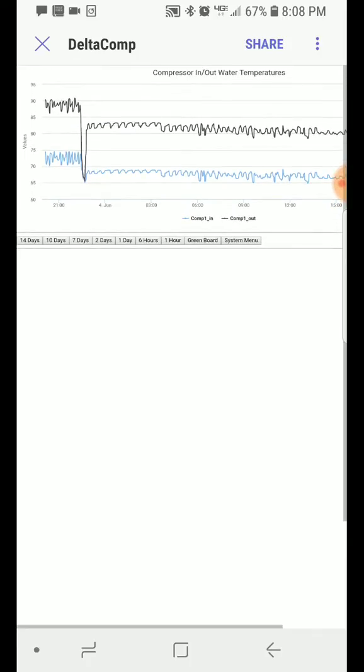So if this were chiller overheating before all of this happened, then the blue line would be going up before they came together. If this was a power related issue on the chiller and the cold head compressor at the same time, then that outgoing temperature would meet the incoming temperature. The black and the blue line would come together, but much slower because the pump isn't running anymore, so it's not transferring heat very quickly anymore.